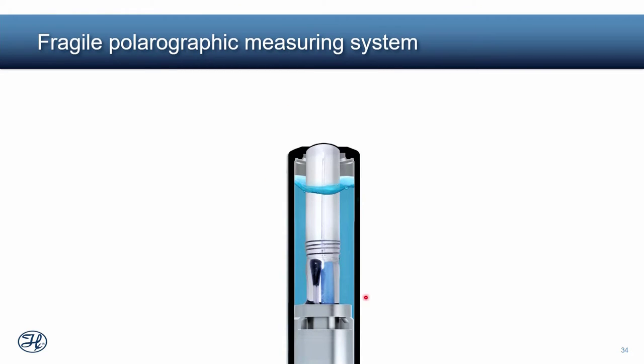So if we look at the inside in this diagram, there's the cap I told you about. There's the anode cathode assembly. Okay. You can see the very fine wires. Those are the silver chloride wires. And there's actually a very tiny point at the top. That's where the platinum comes out. This is a pretty fragile system. And the reason why we stopped using these is because they're very maintenance heavy. This membrane needs to be replaced regularly because the diffusion potential for oxygen across that membrane will change with age. Okay, so you don't get the same oxygen diffusion you did the first day as you did the last day.